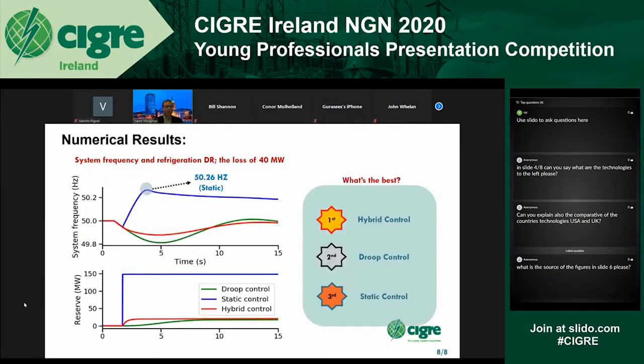And now for the same system setup, a 40 megawatt unit instead of a 20 megawatt unit is tripped. So we can see when the frequency goes below a threshold, the full demand response is activated in the static case, resulting in the best nadir improvement, but with a major drawback of over-frequency overshooting. The response magnitude of the static case greatly exceeds the size of the event. However, in contrast, the hybrid and droop responses are as might be expected, with the hybrid response actually offering a faster active response. But finally, what's the best scheme?